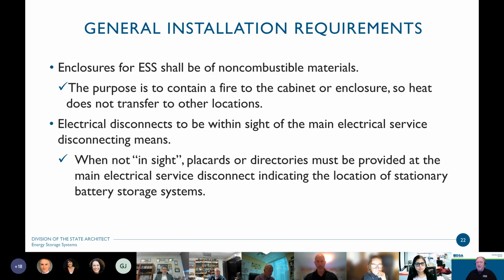Electrical disconnects for the system need to be within sight of the main electrical service. If it's not in sight, code will require placards or directories be provided to identify where these disconnects are, so that emergency first responders can shut these things down.